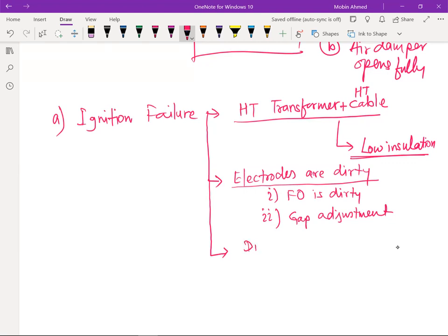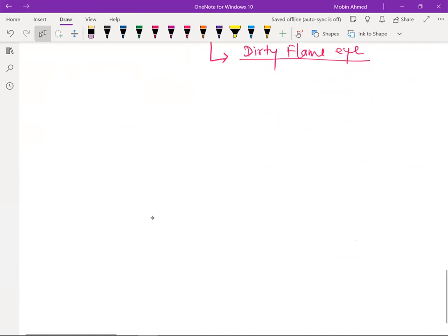And finally, dirty flame eye. This is not a problem that comes only sometimes, because if the flame eye is a problem, it will always give a problem, not only sometimes. So ignition failure will be a problem. Misfire: if there is an alarm and a trace of the misfire, then you should also check this one. And this is again due to the dirty flame eye.